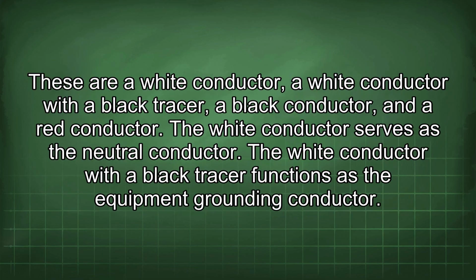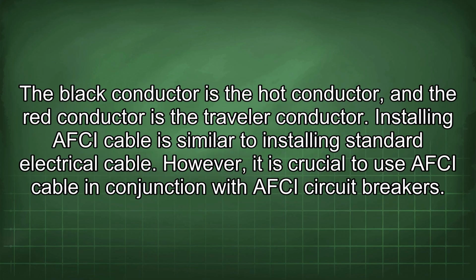These are a white conductor, a white conductor with a black tracer, a black conductor, and a red conductor. The white conductor serves as the neutral conductor. The white conductor with a black tracer functions as the equipment grounding conductor. The black conductor is the hot conductor, and the red conductor is the traveler conductor.